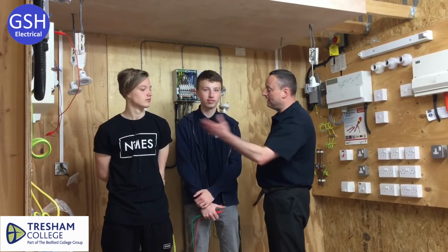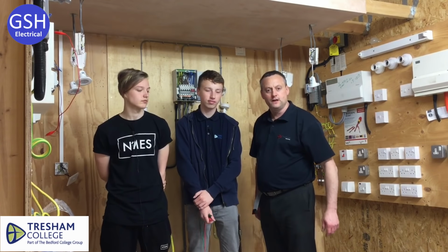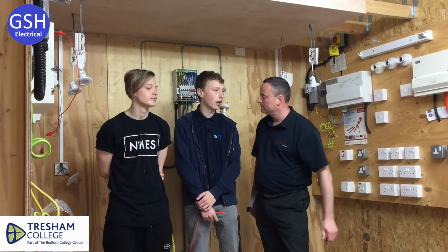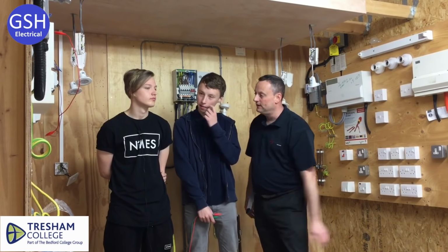All right. So I popped upstairs where we've got Harrison and we've got Logan testing the circuit installed by Ben and Miles. It hasn't gone live yet and it hasn't been tested. They've left it in a position where we're ready to test it. So which test are we going to carry out first, Harrison? Continuity of CPC. Good. Which test will we include at the same time, please, Logan? Polarity. What do you put in the polarity box, Logan? A tick. Good. What does R2 stand for, Harrison? That's CPC. And R1? Line. Of all the readings we get, which one will we record, Logan? The highest. Good. And where would we expect that to be logically in a radial circuit?